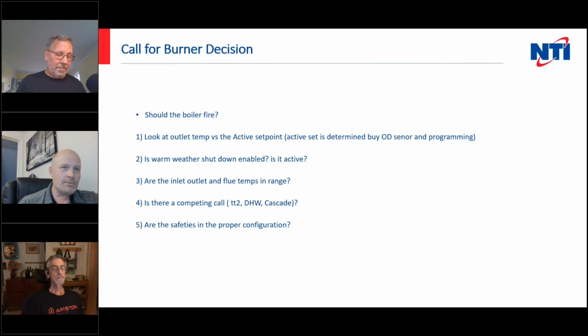Another good practice to get into, go through all the inputs and outputs on the boiler. So you want to look at inlet temperature, outlet temperature, stack temperature. If you have a flow sensor on the boiler, check to see the status of it, assuming it's something you can see. And make sure these things seem reasonable. Touch the pipes, stick your flue analyzer in the flue test port and see if the flue temperature seems reasonable. Sometimes the answer is really simple. The boiler's just got a bad sensor or bad wire harness, and it gets overlooked because it maybe isn't bad enough to give you an error code, but it is enough to stop the boiler from functioning.